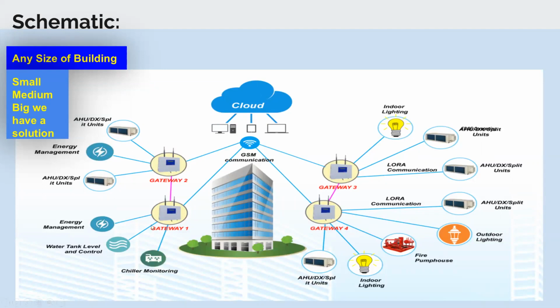For example, each and every utility has its own wireless module. They capture the data and send the data wirelessly to the smart communication manager console and gateway. In short, the gateway acts as a bridge between these wireless modules and the cloud. So when we do a complete survey, we divide the area into multiple parts, and each area is allocated a gateway. The data gets received at the gateway and sent to the cloud through GSM communication. So like that, the entire building is covered. And please note, sir, all our modules are edge computing modules, where each and every controlling module has the inbuilt understanding and controlling capability based on the parameters.